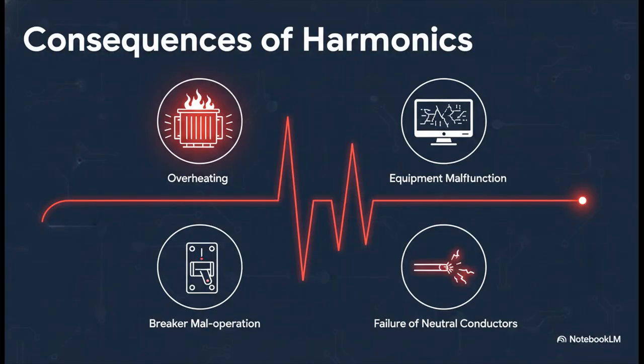All that extra harmonic energy has to go somewhere, and a lot of the time it turns into heat, causing cables and transformers to dangerously overheat. It makes sensitive electronics act up, trips circuit breakers with no obvious reason, and can even cause neutral wires, a critical safety feature, to fail completely.